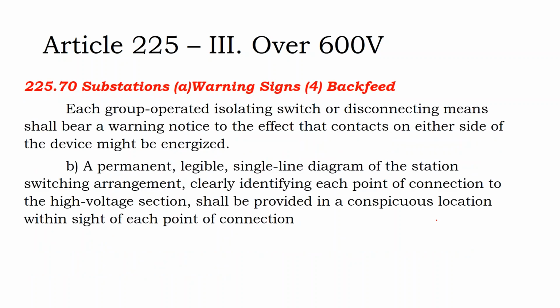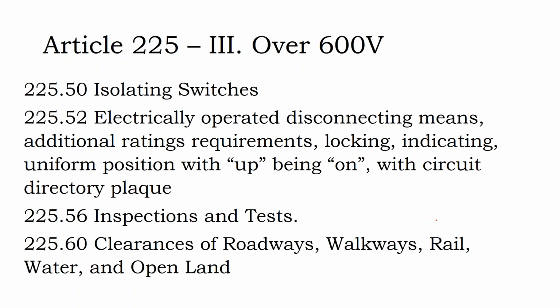That also applies on a panel board. You know, up is on, down is off. You know, that's what this is visually indicating. If the switch is side to side, you know, right on, left off, that's not considered indicating. So switches need to be in vertical positions where they're visually indicating, with up being on and down being off.